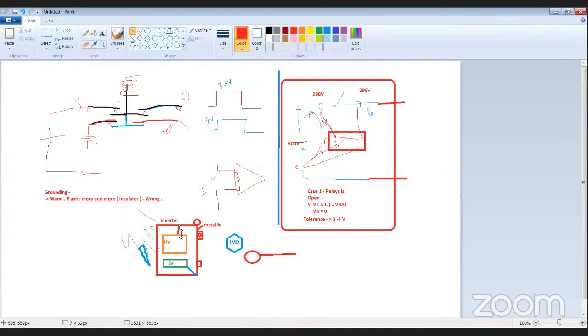This is not something which will happen normally, but if it happens and you touch it, you could get a shock. To detect this we have IMD. What IMD does is it has a ground connected to this ground, and it continuously monitors these HV cables, HV plus and HV minus. So it continuously monitors these three signals, and as soon as something happens, it will detect it and trip the HV. Wherever this HV is supplied to a component, it will open that circuit. This is the primary role of IMD.